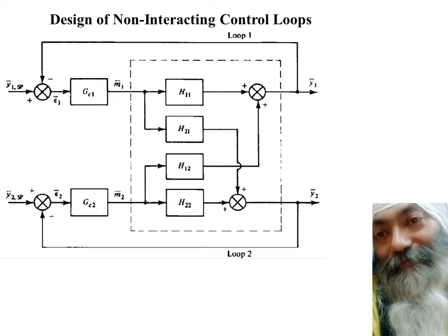variable. But even after that, we found that in case the relative gain array is something like 0.5 or 0.6 or 0.4, it can cause a lot of issues in controlling the system, as the effect of one loop happens to be on the second one.